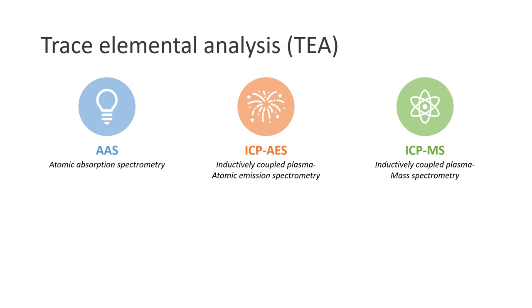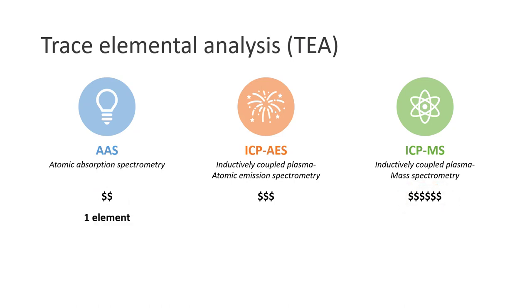So which one is better? Well, it depends on the purpose and the budget. When it comes to cost, AAS is usually the most affordable, while ICP-MS is the most expensive. Typically, AAS allows analysis of one element at a time, while ICP-AES and ICP-MS allow analysis of multiple elements simultaneously. If you are dealing with simple samples, AAS can be used. If you are dealing with more complex real-world samples, ICP-AES or ICP-MS may be a better choice.